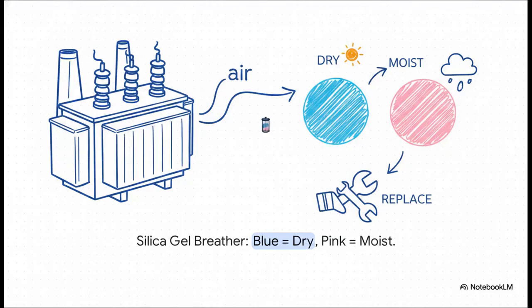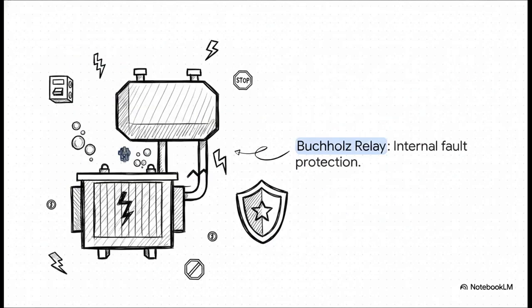Now, connected to this system is the silica gel breather. And this right here is a totally critical visual diagnostic skill for any plant operator. When the transformer breathes in air from outside, this gel absorbs the moisture. Here's a pro tip to remember. If the gel is blue, you're good. It's dry and healthy. But if it turns pink, it is totally full of moisture and needs to be replaced immediately. Right between the main tank and that conservator tank sits an absolute safety legend, the Buchholz relay.